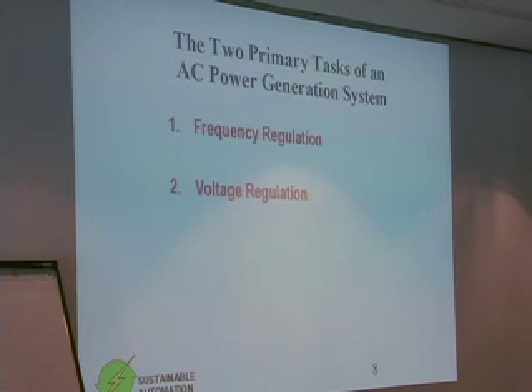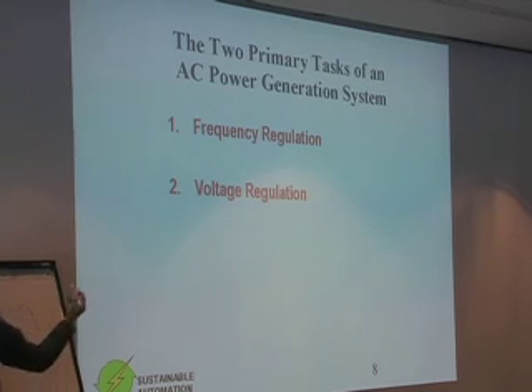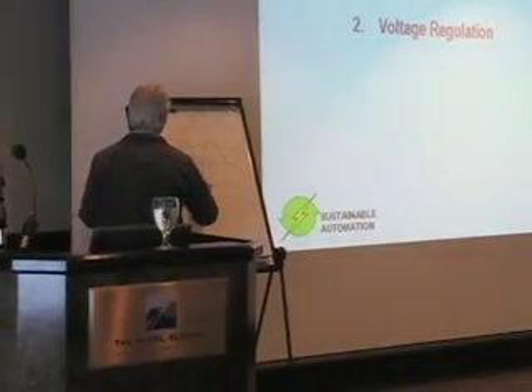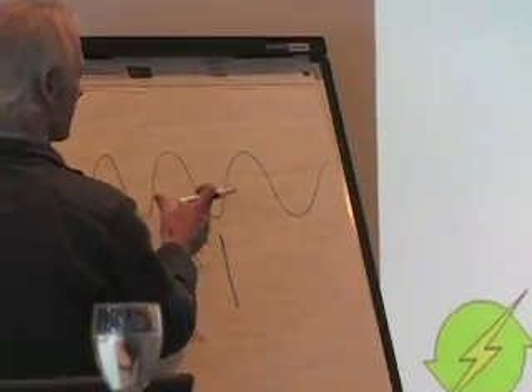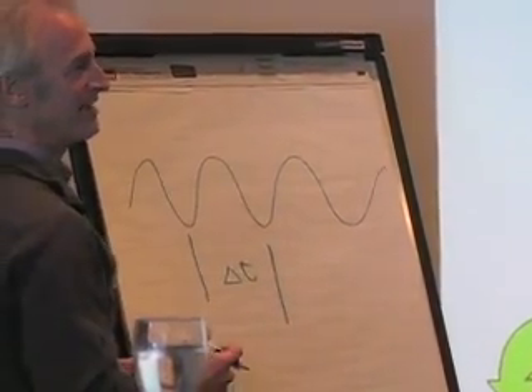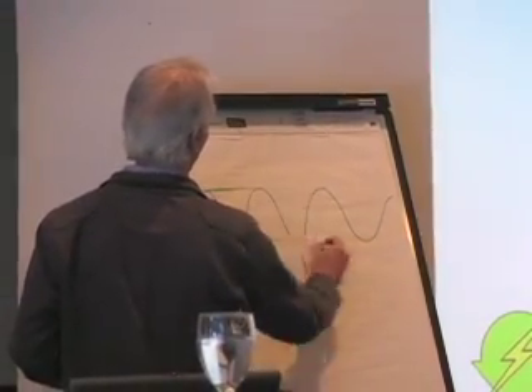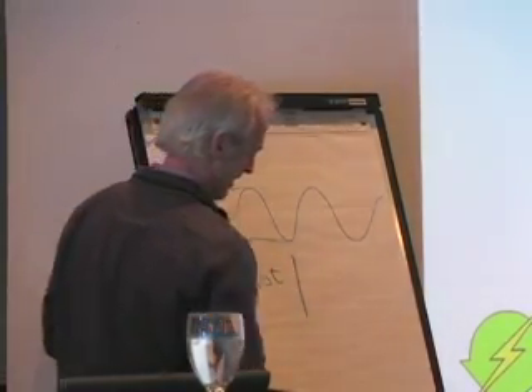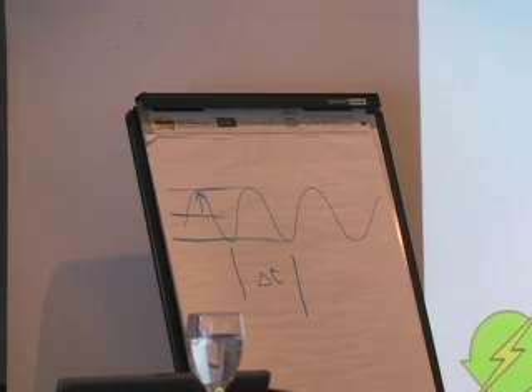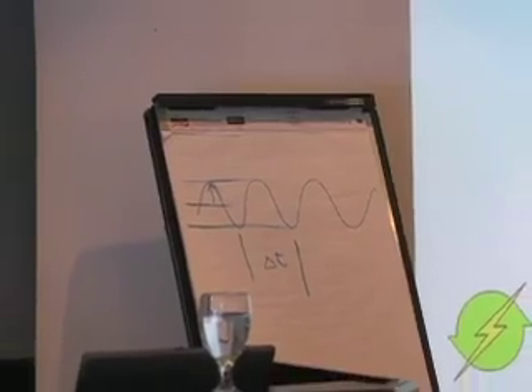Well, fundamentally, and this is a utility's job, it has to regulate voltage and frequency. Wherever you plug in that appliance or connect that machine, you've got a well-regulated voltage and frequency. The utility's done its job. The rest is just billing. So basically, you've got your voltage waveform. Frequency, the period of those cycles, you want that to stay constant. You want a constant 60 hertz. And the amplitude of the voltage, you want to be fixed at whatever it's supposed to be, whether it's a 480 volt system or 600 volt system, whatever.